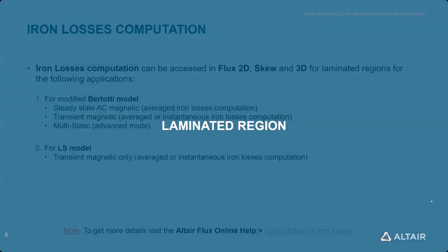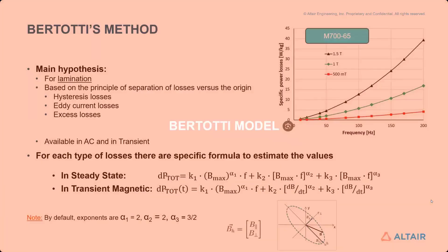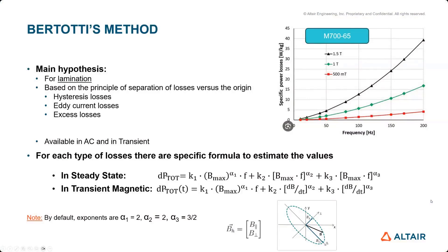For laminated regions, we have two models. The Bertotti model works in all different applications — transient and static. The LS model is only in transient. Both can be used in 2D, skew, and 3D. Focusing on the Bertotti model, this is the main iron loss model you'll find, and it can take different names depending on where you look. We have curves of losses per kilo versus induction and frequency, and this model tries to fit these losses, taking into account hysteresis losses, eddy current losses, and adjusting the value with excess losses. You have three k coefficients and three alpha exponents to quantify the different losses at different frequencies.